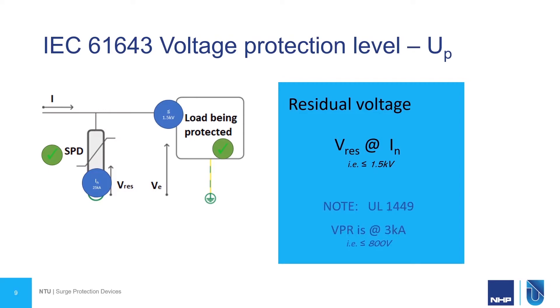A note on this point: UL1449 is the North American standard for surge protection devices. It has a similar unit called VPR. The point that differs here is that this is tested at 3 kA, not at IN. Therefore its values are generally a lot less — generally less than or equal to around the 800 volt mark. So on paper that looks more impressive, however it is a different test.